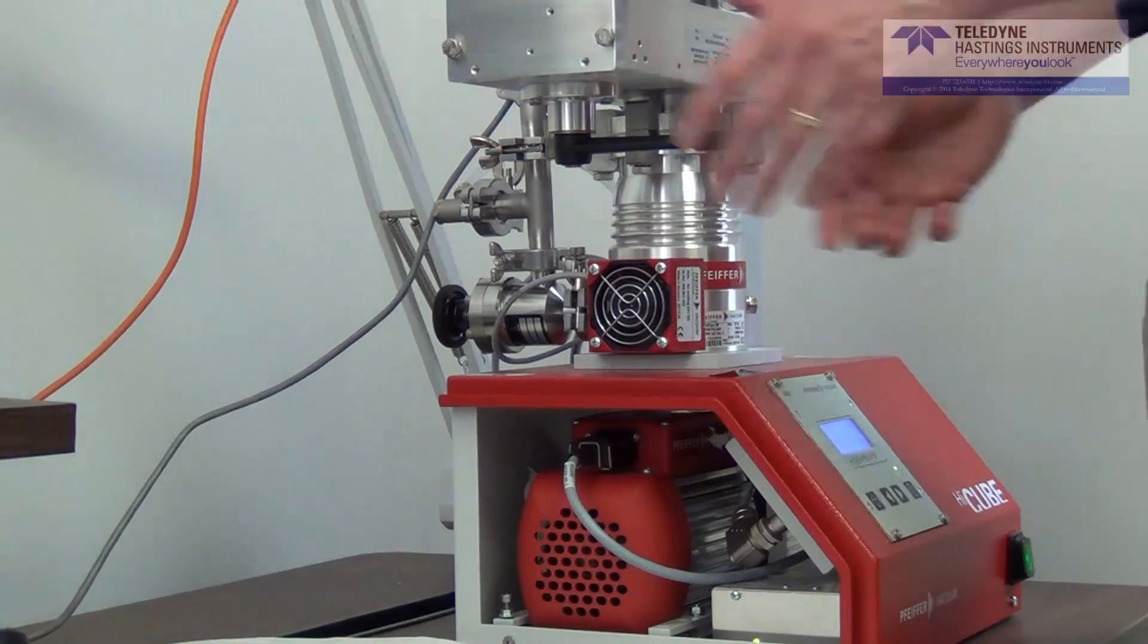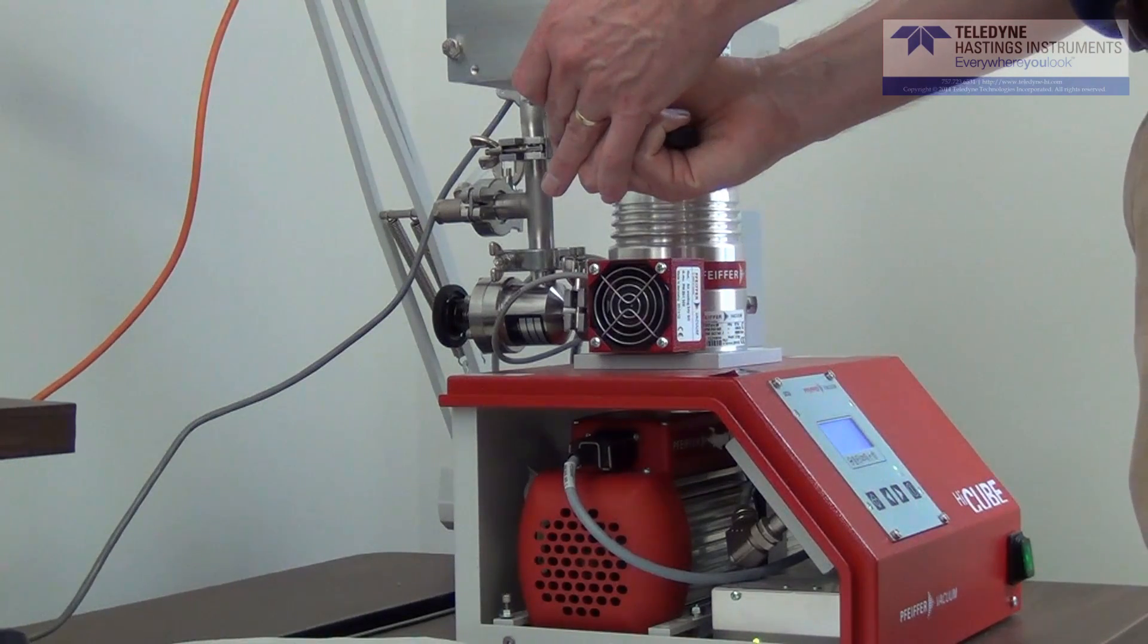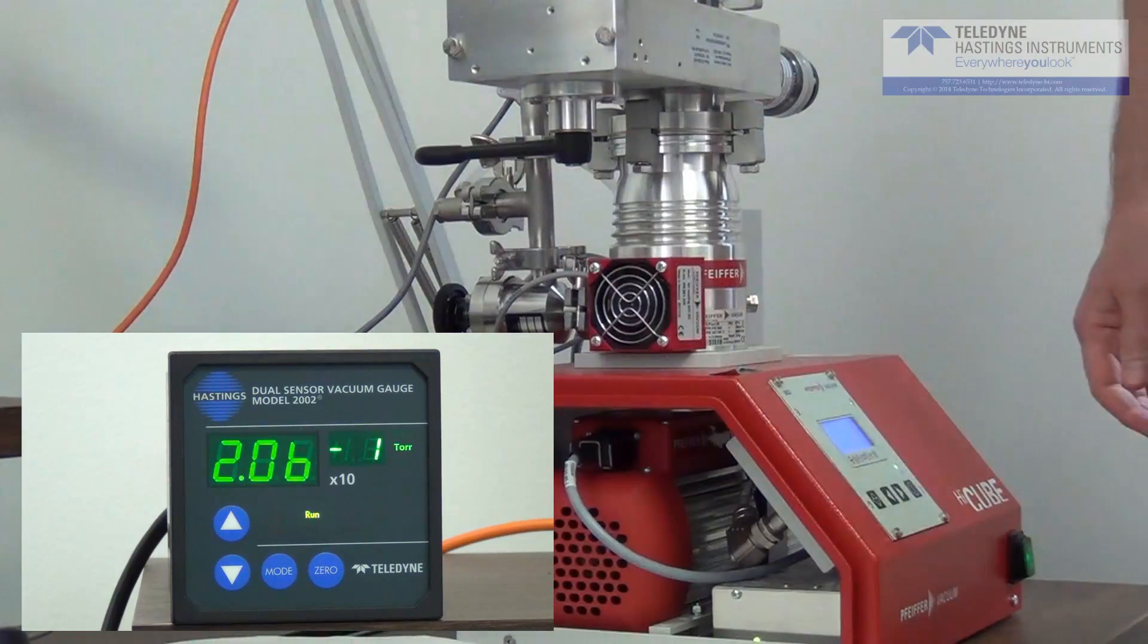Down to 10 torr. And you just see that the set point light just went out. And we've passed 8 torr. Now we're looking at only the thin film Pirani sensor. So now we're below 3 torr. And I'm going to go ahead and throw the main gate valve. And you'll see that the HPM 2002 responds very quickly to the changing pressure.